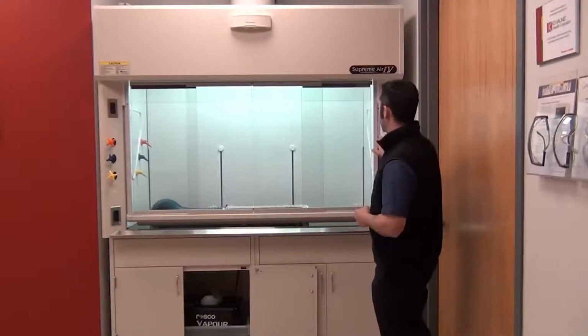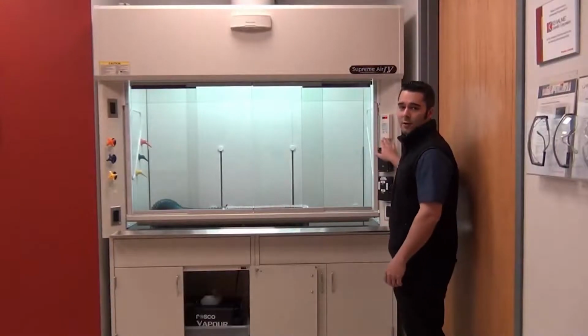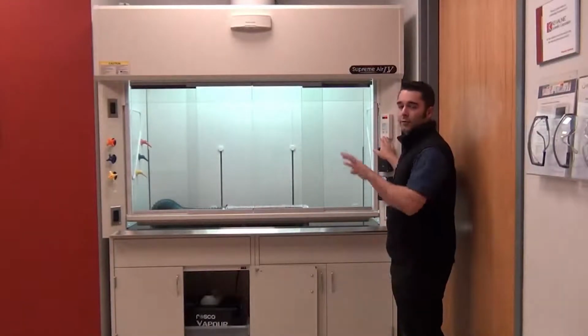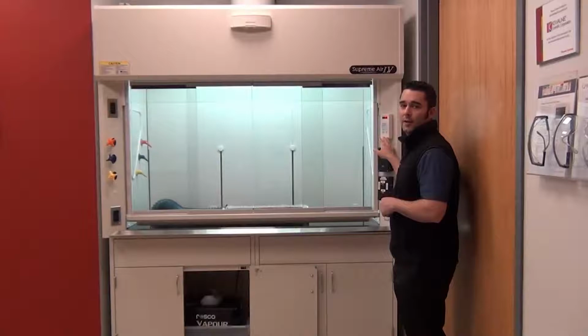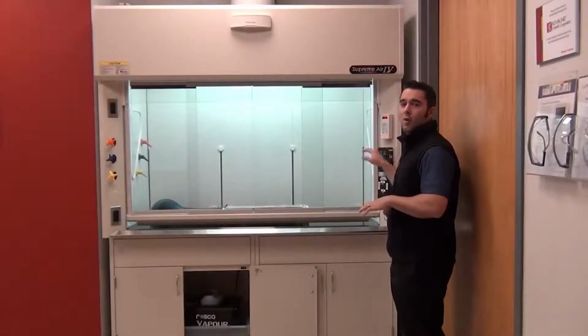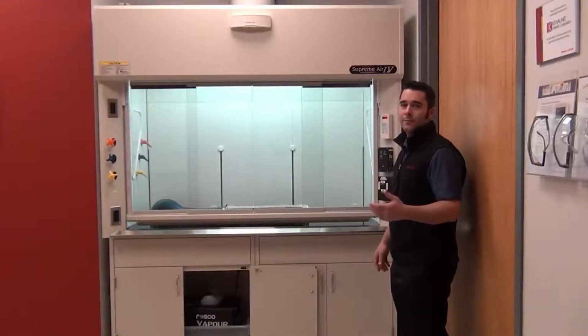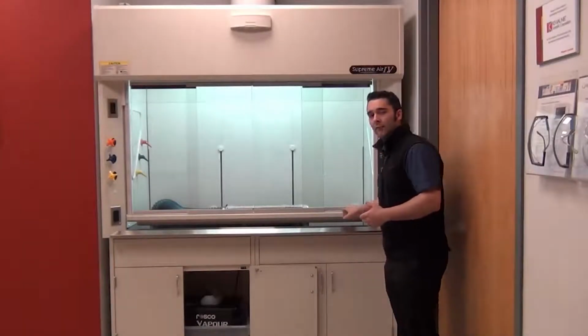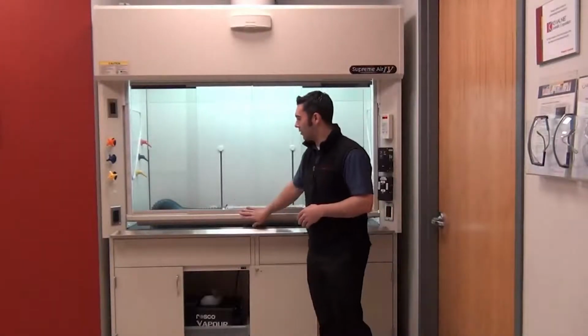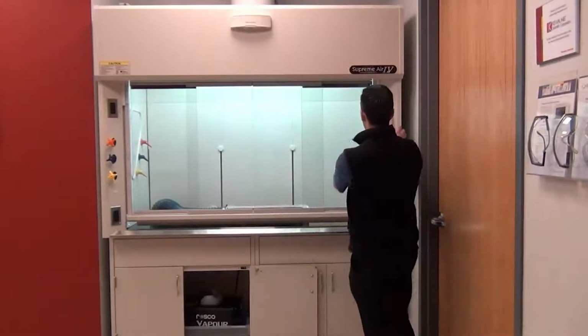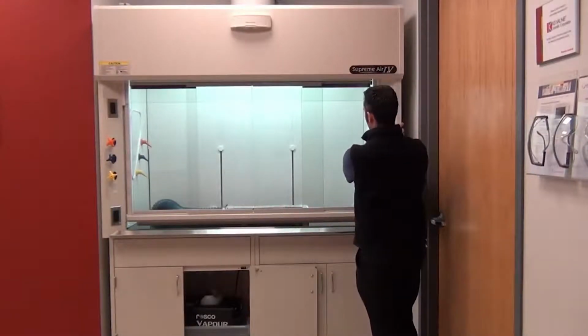So through the Phoenix Controls monitor, this is an older monitor, this is a 631, or through the Sentry monitor, which I'll show in a little bit, either one of those monitors, or through a building automation system, or if you wanted to hardwire a key switch on the wall, I can verify that this sash is 100% closed, there's no chemicals in the fume hood, and I can actually send this device to a full shutoff mode.